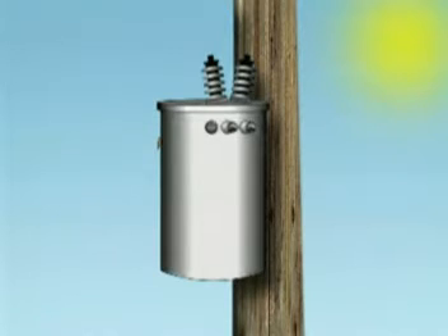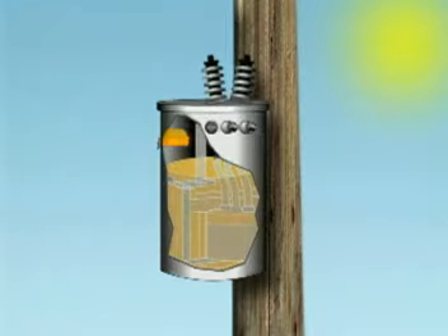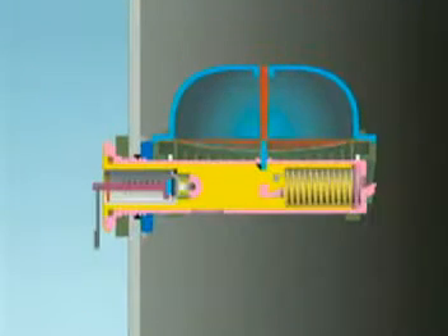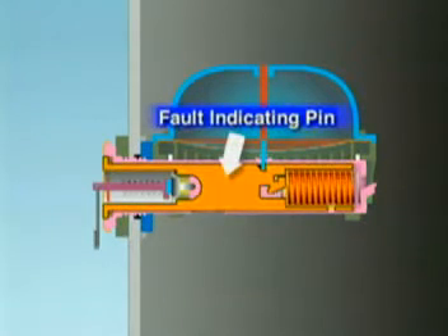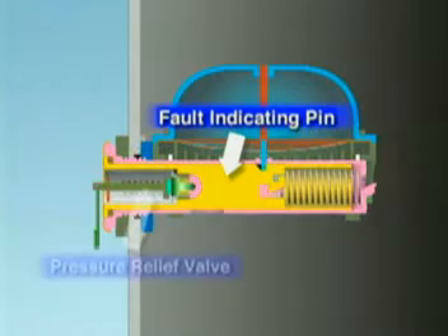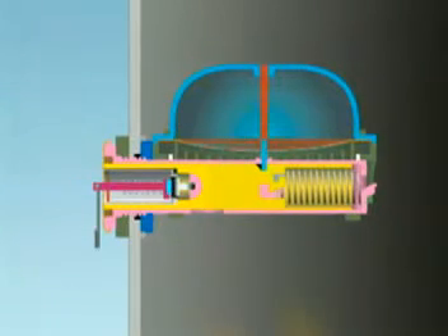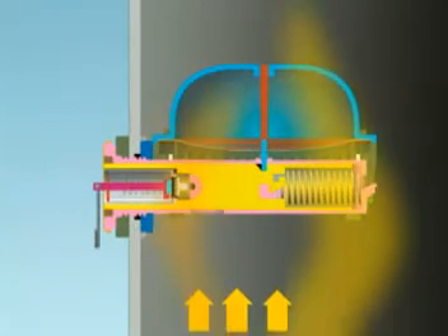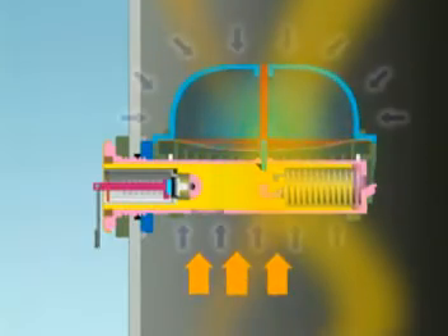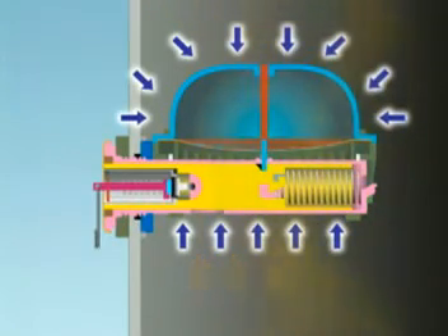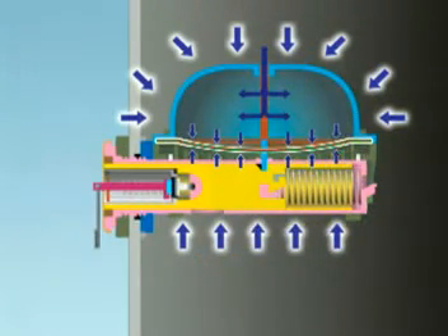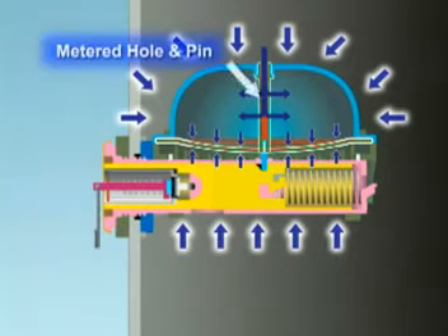Here's how the IFD works as a pressure relief device. During a hot day or heavy loads, the transformer heats up. This causes a slow rise in the pressure, which will activate the PRD should the pressure go above the specified PRD activation value. As shown here, the heat rises in the transformer, causing pressure to build up slowly. As the pressure increases, it is able to equalize on each side of the diaphragm through the metered hole.